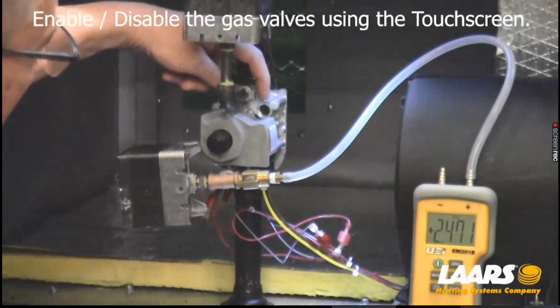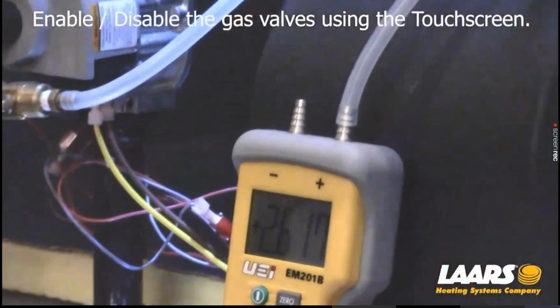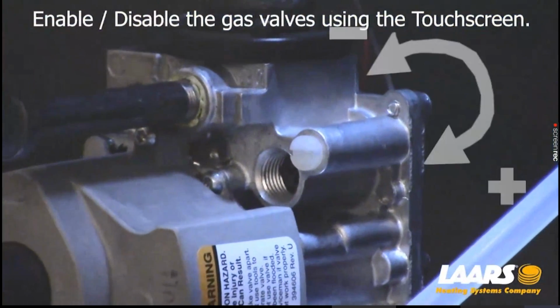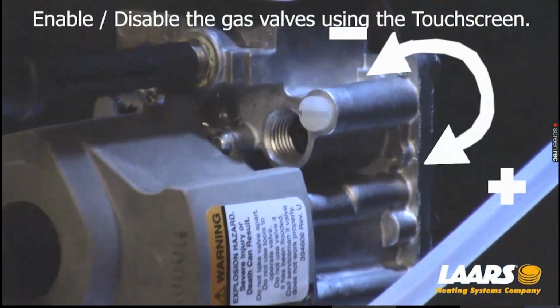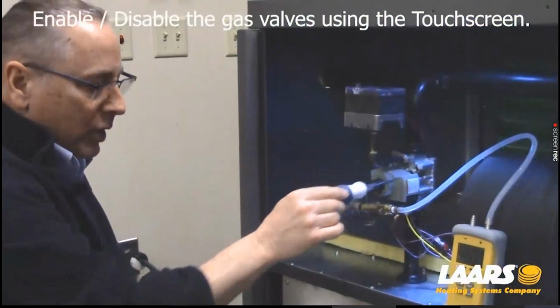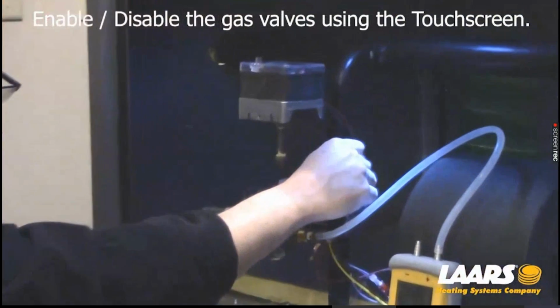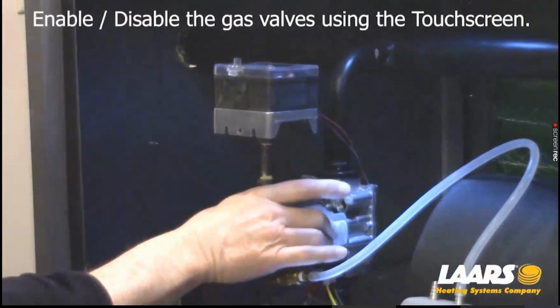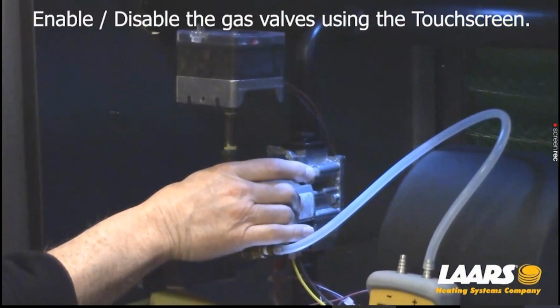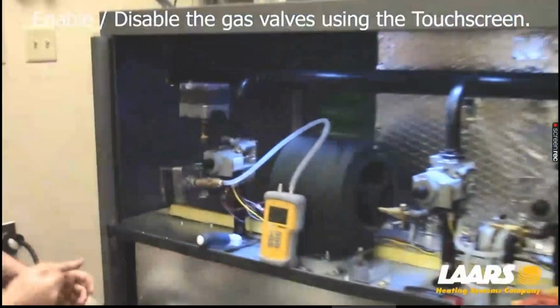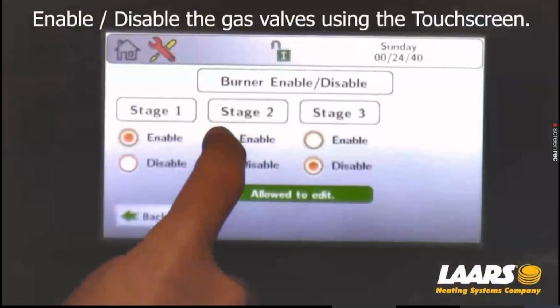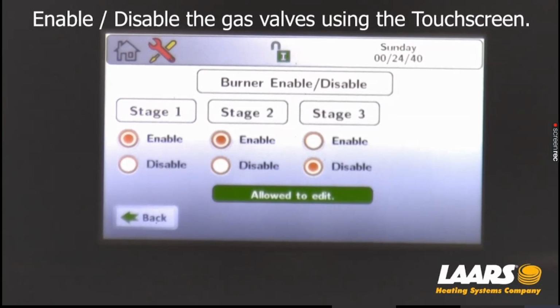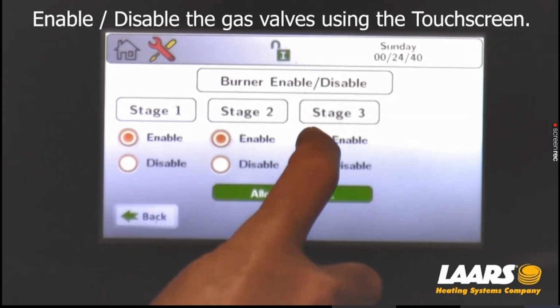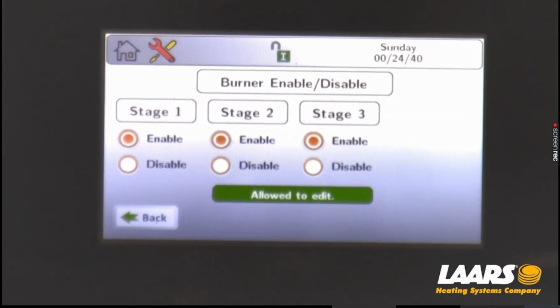A couple of tenths is not a big deal. If not, here under on your gas valve, there'll be an aluminum cap. Take the cap off, make an adjustment with your screwdriver. When you're done, the aluminum cap should go back on. So now valve 1 is checked and set. I have to do this for all 3 valves in this case. I'll enable valve 2, check that one, and then we'll come back into this option and enable valve 3.